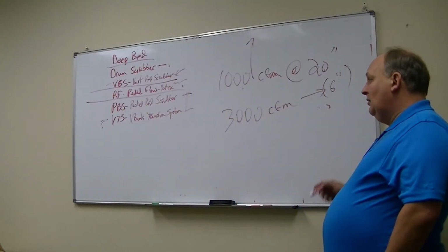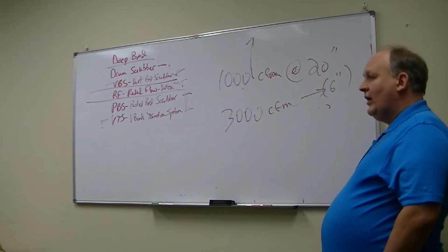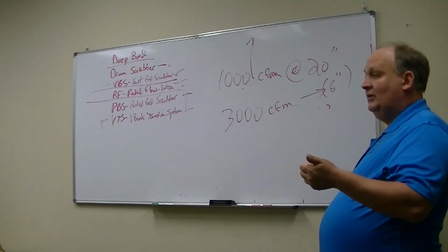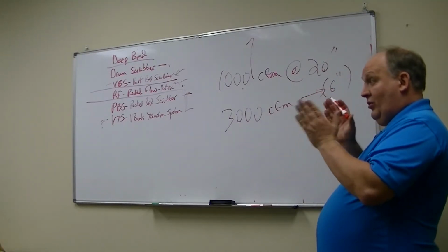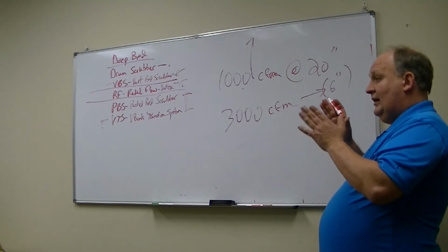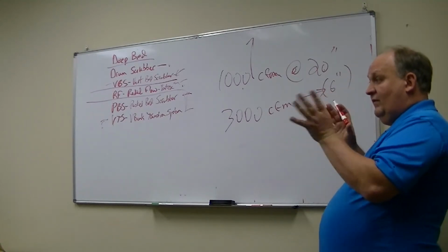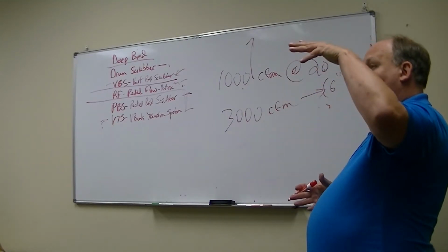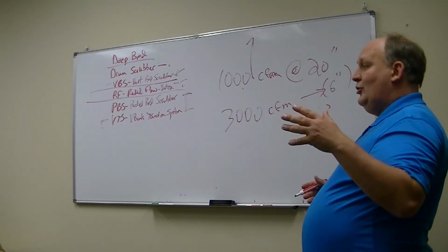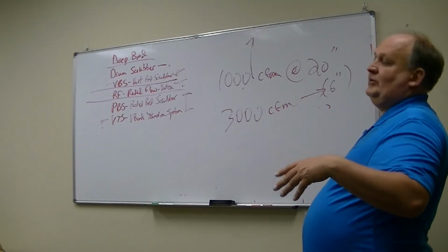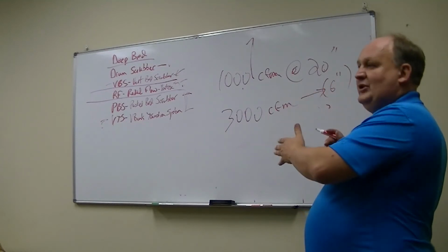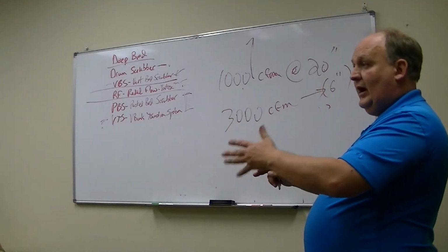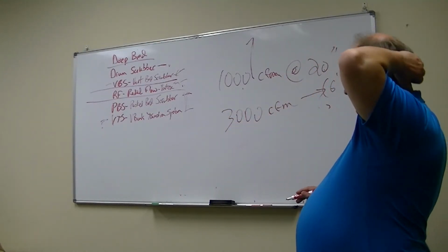So then you're saying, well, what's wrong with too much airflow, right? Now that's all sorts of problems. Remember your mist and grease filter. It's got to operate within that zone of 300 to 350 feet per minute. So if you've sized your airflow on 1,000 but you're actually getting 3,000, now your pressure drop going through your mist and grease filter is going to go through the roof. And you're not going to capture any of the water going into it, because the water drops are going to race through there, right? So that becomes a problem.